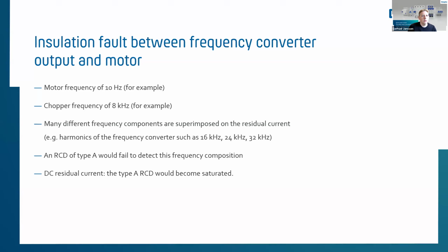For example, the harmonics on the frequency converter: there are different harmonics causing such problems, at 16 kilohertz, 24 kilohertz, 32 kilohertz. Doepke even has a system to visualize those frequencies or harmonics. So you can visualize the different residual currents in the system to see what part of the frequency gives you the trouble, gives the breaker the threshold to trip, and how to prevent it.